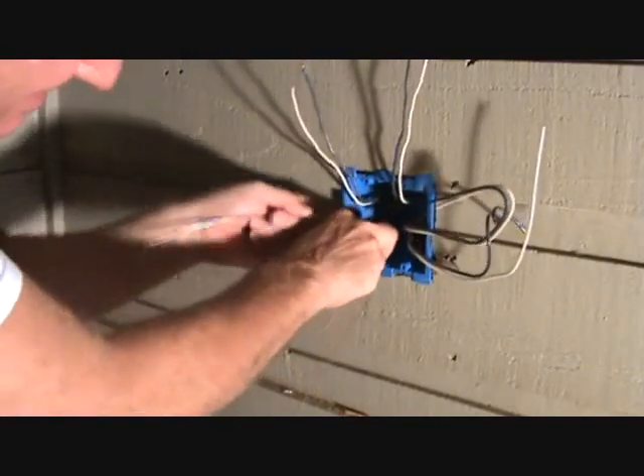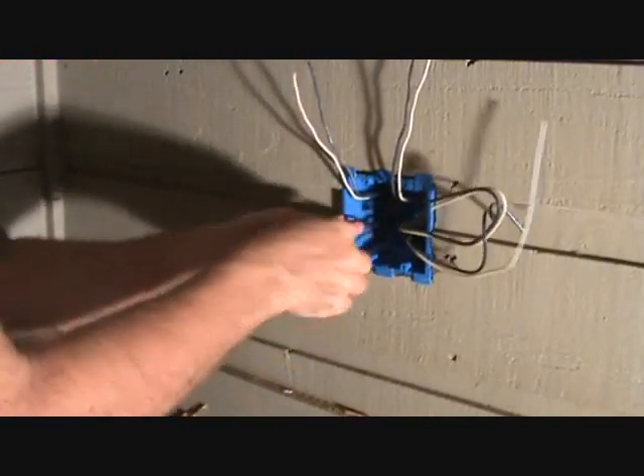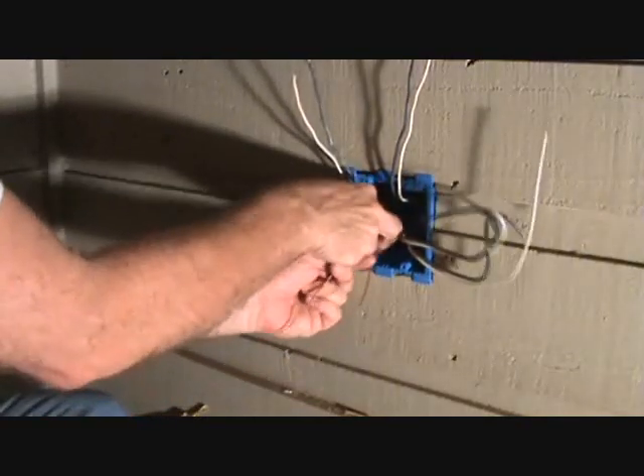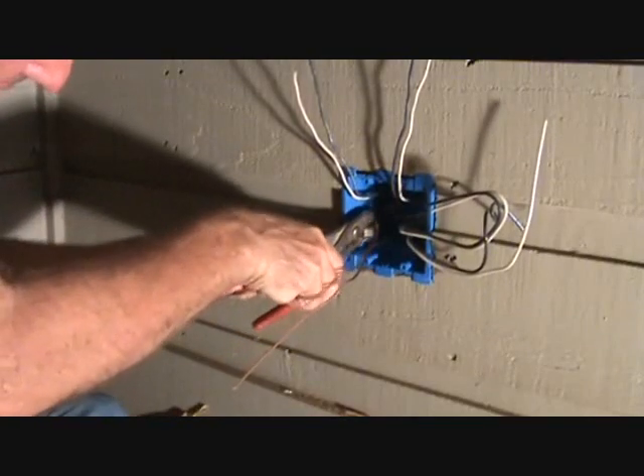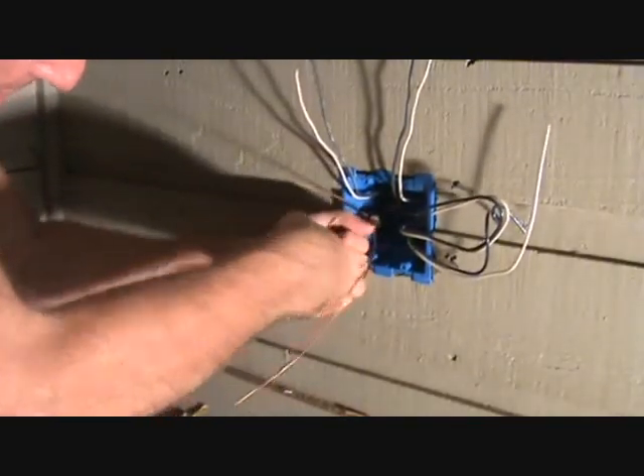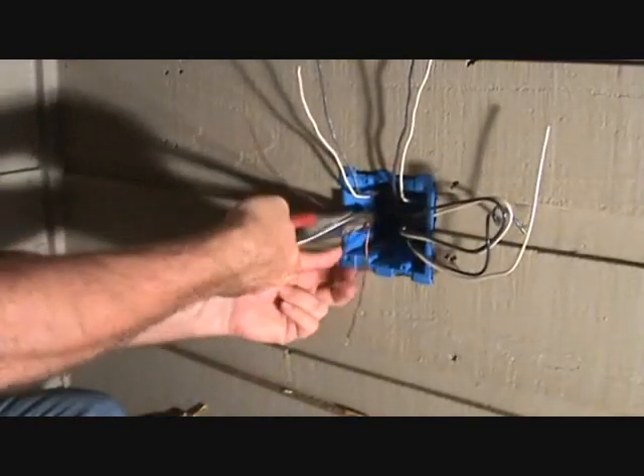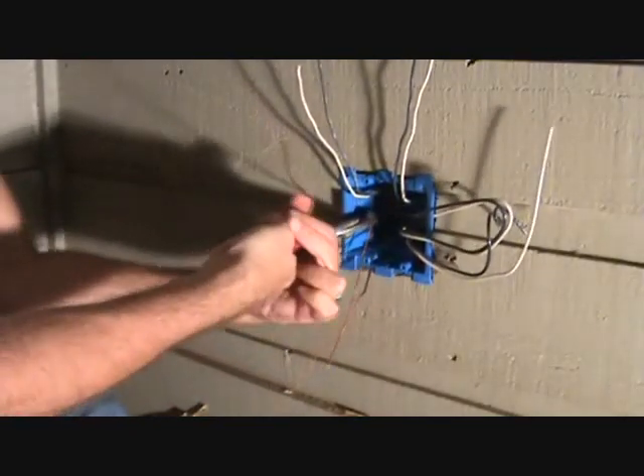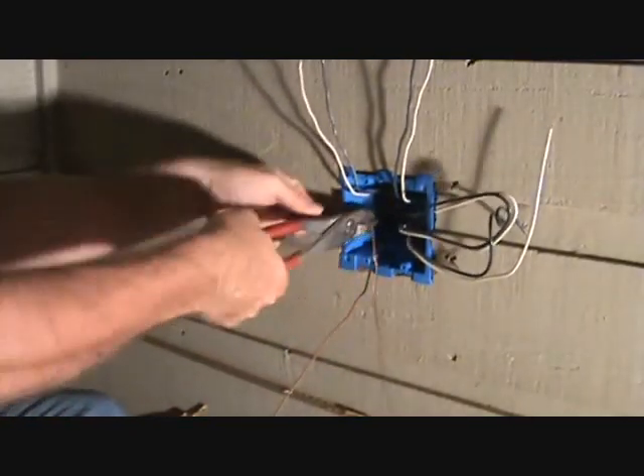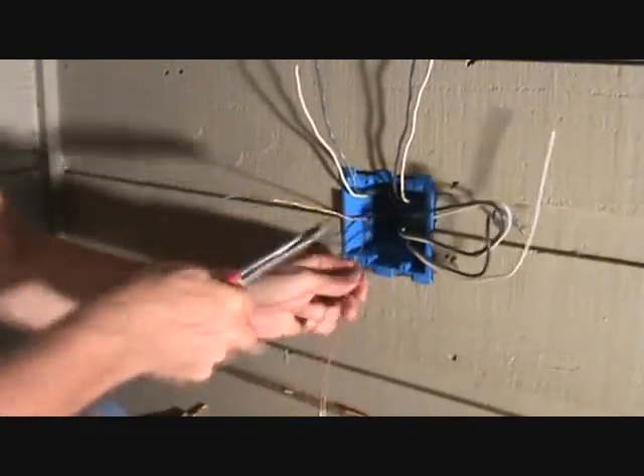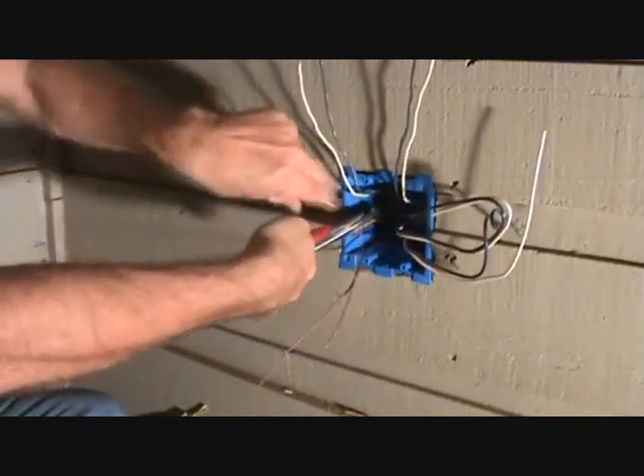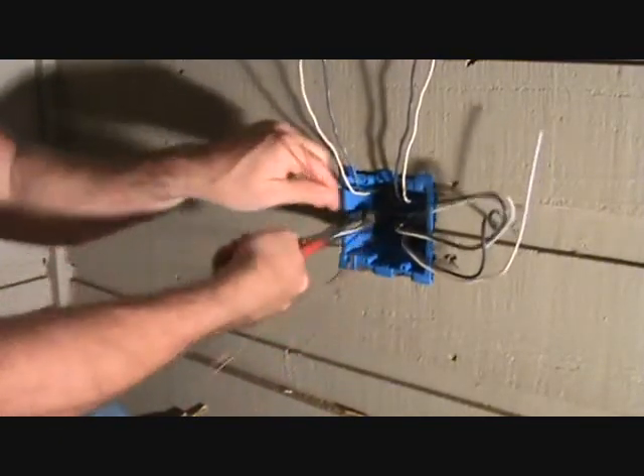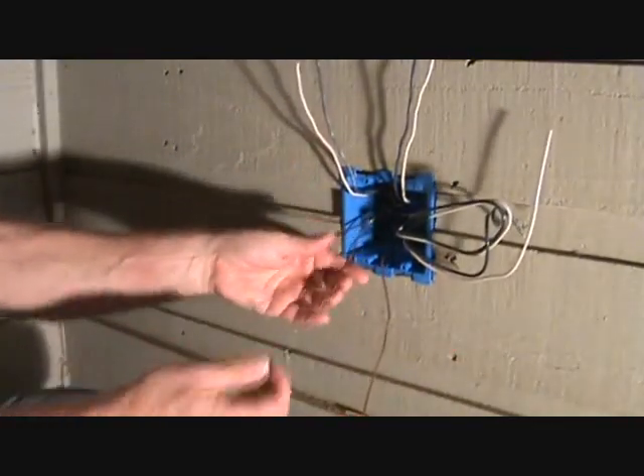Before I slide that on, I'm going to twist this around a few times. Make sure your ground wire is pushed all the way back there. This kind of helps connect it together. You want to do that a few times. You don't want to do it too many times. If you do it a whole lot of times, you could snap it, you could break it off, the ground wires. So give it a good few twists there.